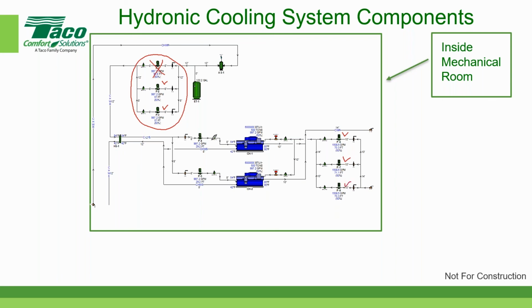The logic behind having only two chillers on the primary side of the chilled water distribution, where the chillers are: for commercial, this is where you have to make your decisions based on a whole series of economic analyses. But generally speaking, two chillers sized for 50% capacity are usually the most economical for a commercial office building. That's not true of other types of buildings. The reasoning is that the peak load, when the building requires, in our case, 1,000 tons, only occurs about 3% of the time. The overwhelming majority of cooling hours only need between 50 and 60% of the system capacity.